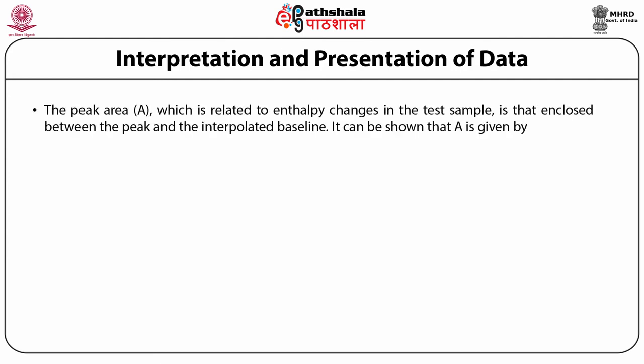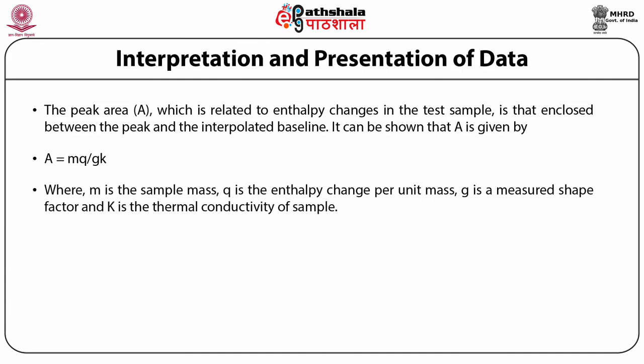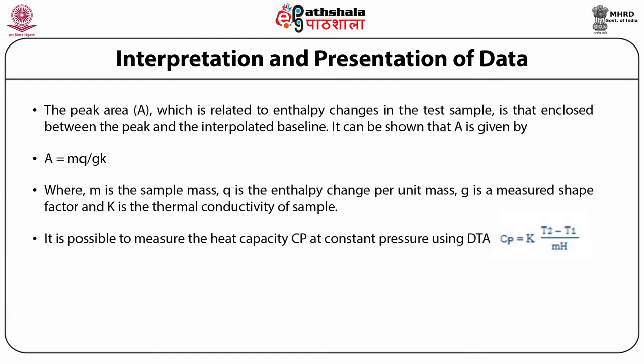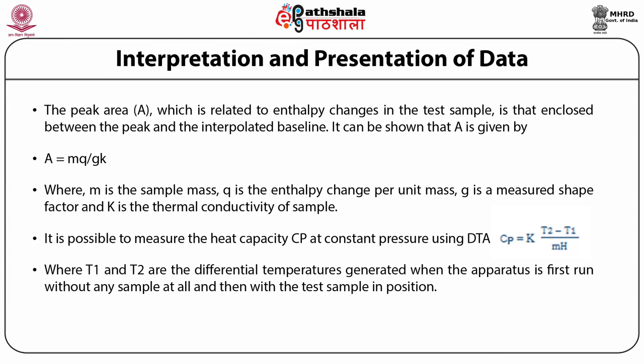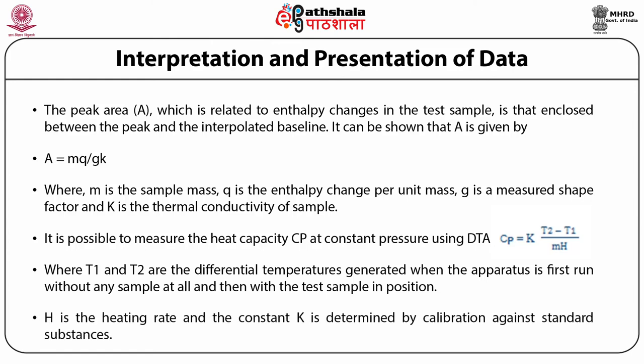Interpretation and presentation of DTA data: The peak area A, related to the enthalpy changes in the test sample, is enclosed between the peak and the interpolated baseline. A = MQ / GK, where M is the sample mass, Q is the enthalpy change for unit mass, G is the measured shape factor, and K is the thermal conductivity of the sample. Heat capacity Cp at constant pressure can be measured using DTA: Cp = K·(T₂ − T₁) / (M·H), where T₁ and T₂ are the differential temperatures obtained first without any sample and then with the test sample in position, H is the heating rate, and K is determined by calibration with standard substances.